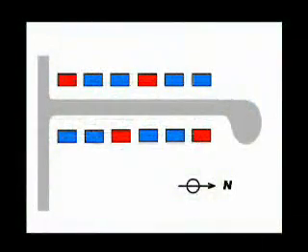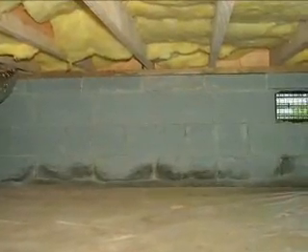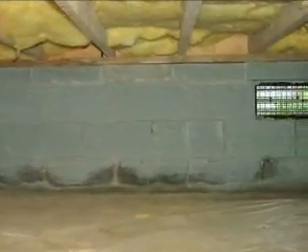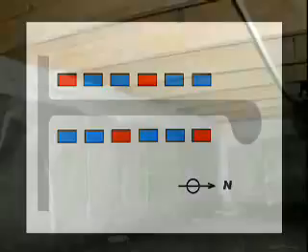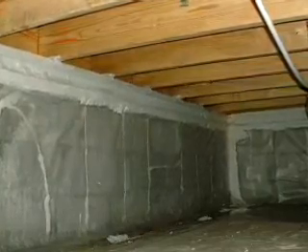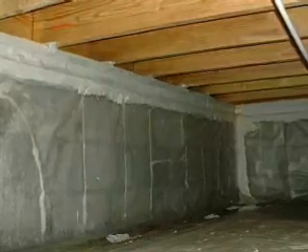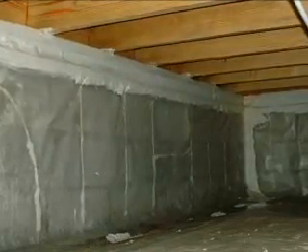The 4 homes in red on the site plan are the control group of wall-vented crawlspaces. The control group has open foundation vents and a carefully installed 6mm poly vapor retarder that covers the entire earth floor. The remaining 8 homes in blue are the experiment group of closed crawlspaces. This group was converted to closed spaces by blocking off foundation vents and air sealing walls. In addition, the earth floor and inside wall surfaces were fully covered by a sealed liner of 6mm poly.